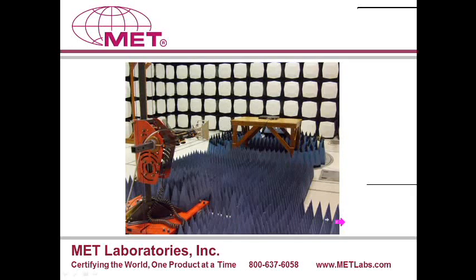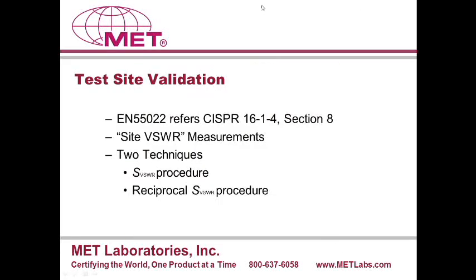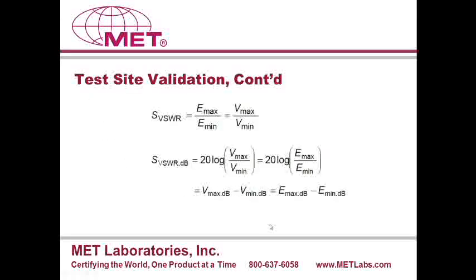Next, I'm going to move to the site validation. For CISPR 16.1.4, Section 8 defines the site validation method, which is based on VSWR. The standard specifies two different techniques: one is the site VSWR method, and the other one is called the reciprocal site VSWR method. Let's explore both these methods.